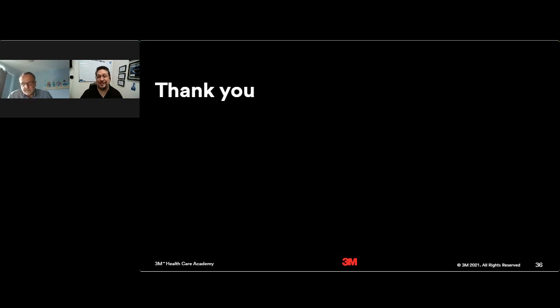Yeah, and I wish I could record that little snippet and take it to facilities departments that I've worked at before, because just about every facilities department I've ever worked in, I would suggest pure water for the boiler. And they would say, well, we put in a water softener, so it'll be fine. And I was saying, well, if you look at my instruments, they're brown, which they're not supposed to be. The inside of the sterilizers are brown. But yes, that pure water, that's excellent advice. And I would advise anybody out there who's struggling with those things to take that advice. Thank you, Dr. Kirk. That was very engaging.